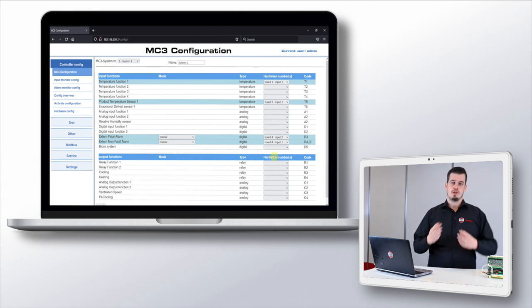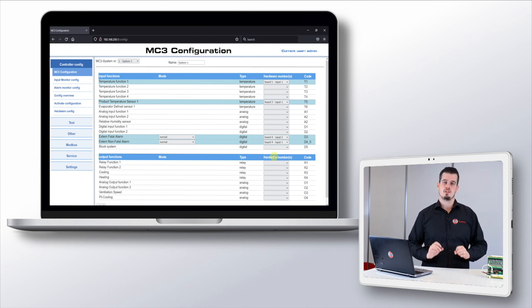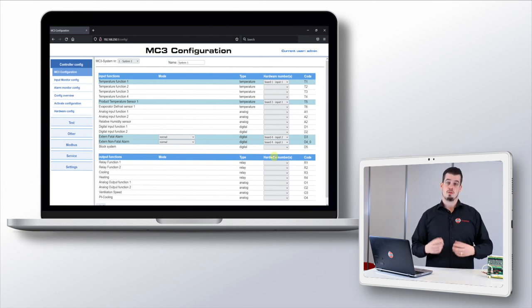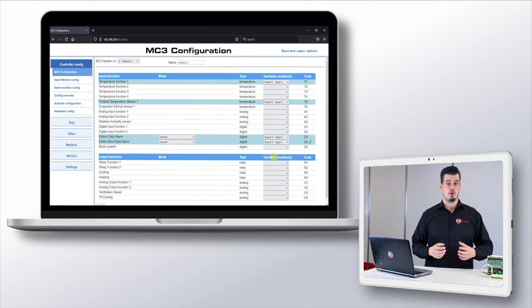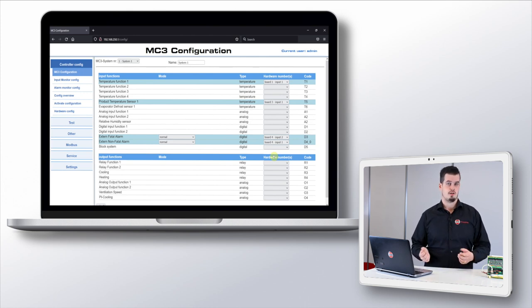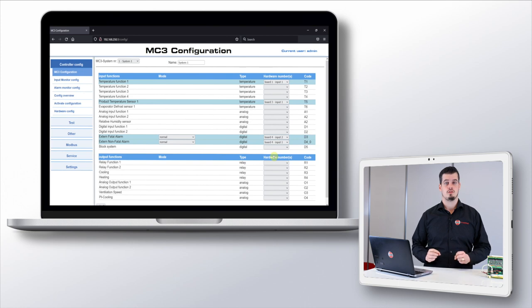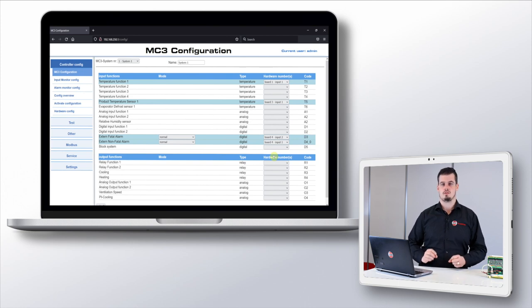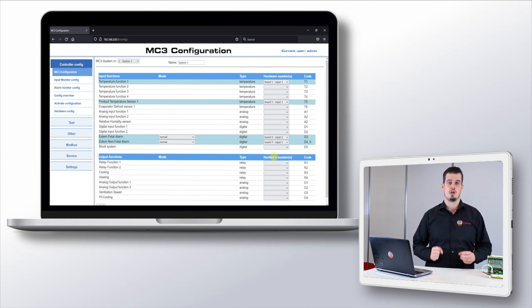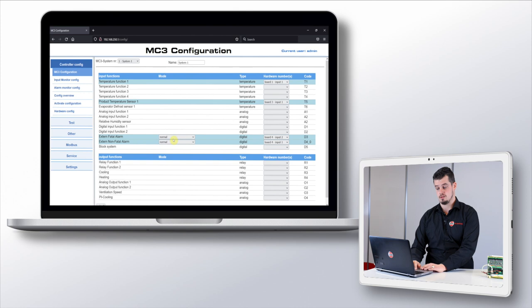When we have done this we can see that there are mode options available for the functions: normal, active when high, and inverted, active when low. Since we want to have an alarm activated when the signal is low, we'll select the inverted option.